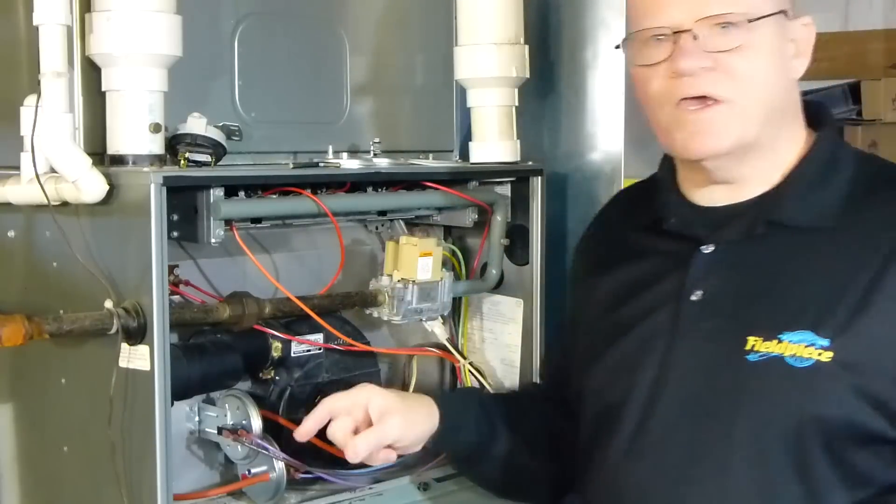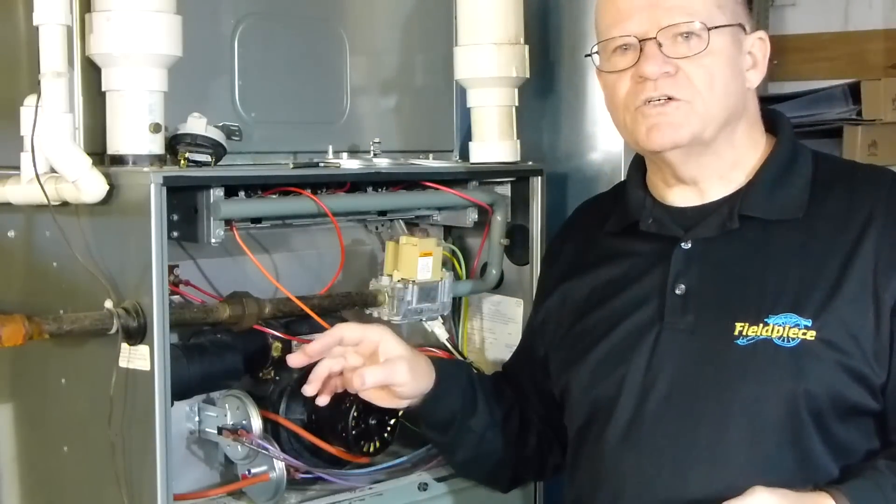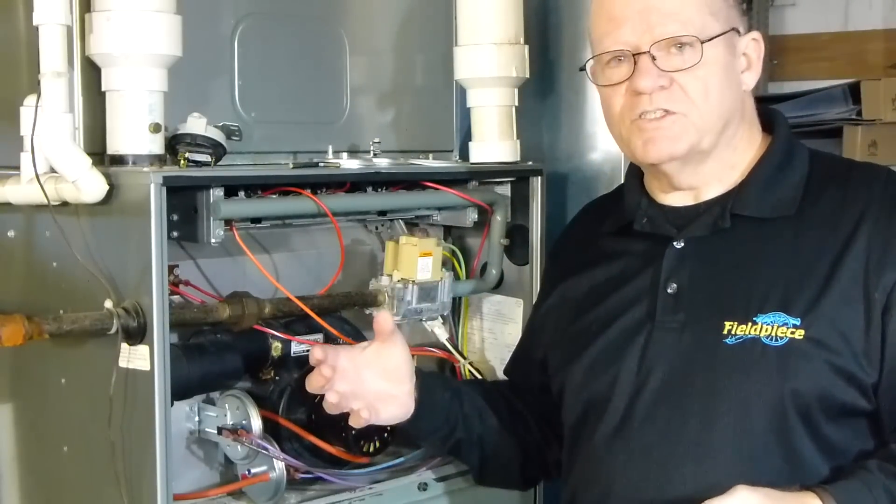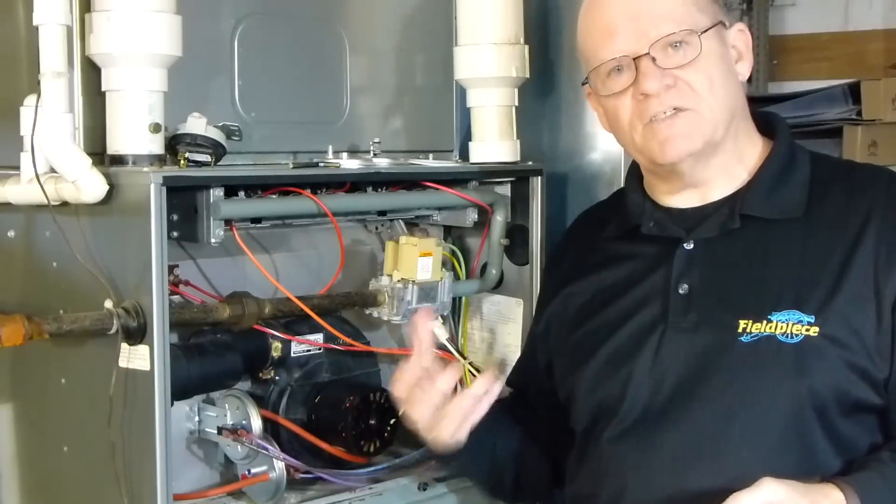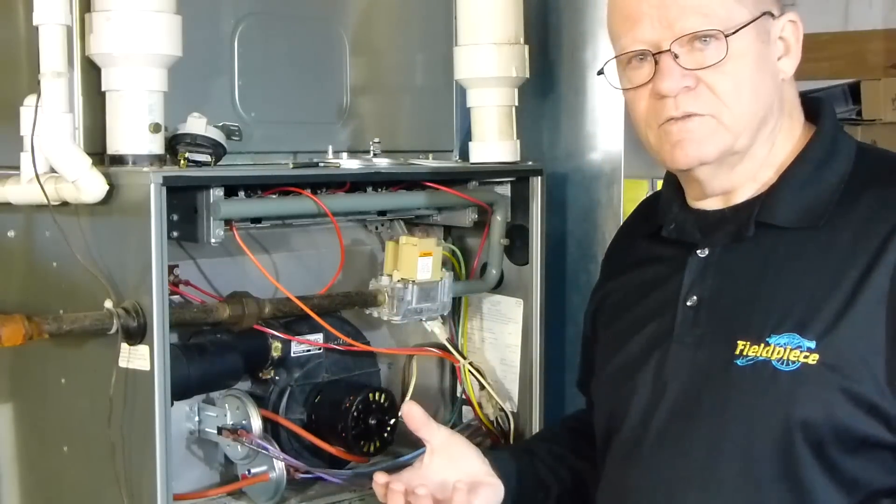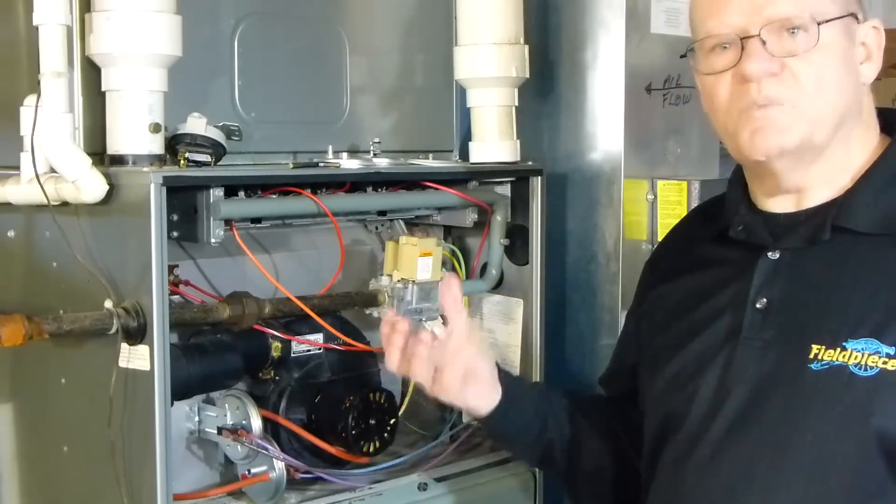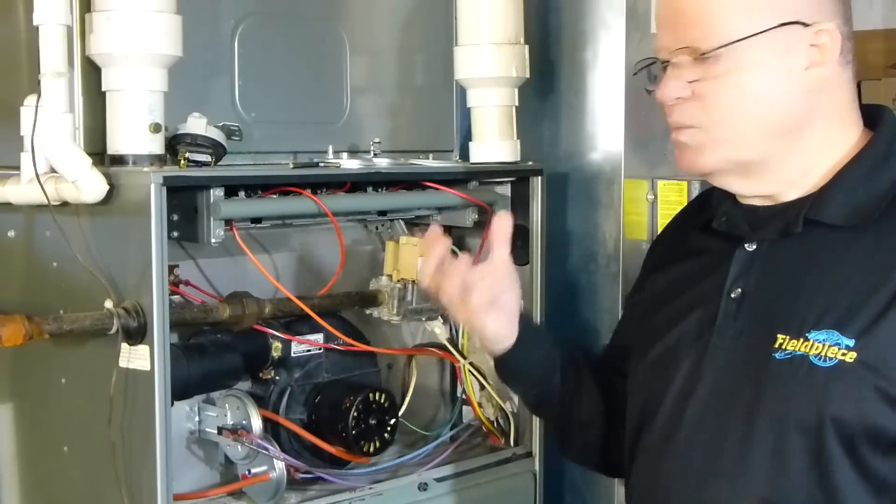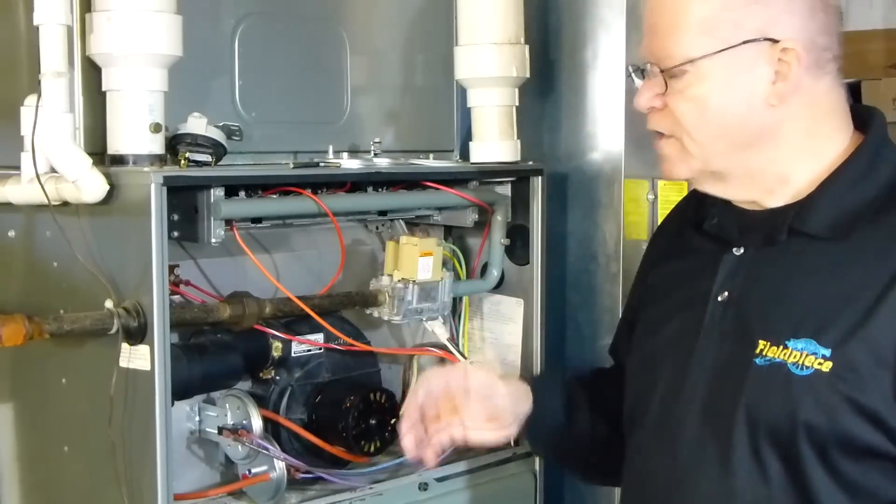I don't care where your pressure switch is located—you can still get moisture in the pressure switch, and that moisture contains the caustic chemicals of the gases. So it's definitely going to play havoc on the pressure switch.